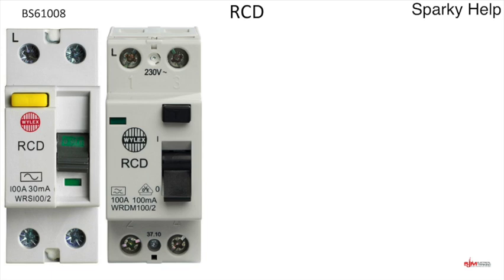What's the difference between the two? The Type A will pick up DC currents as well. Lots of our installations now have DC equipment — for example, some tumble dryers or washing machines have inverter drives in them, which basically means they turn AC into DC and back into AC again to give variable speed motors. Because of swapping and changing the frequency back from AC to DC and vice versa, if you have a fault on those particular appliances, they may not trip the AC type RCD.